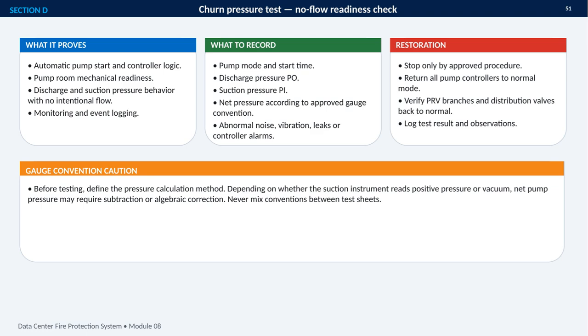During the test, I would record the pump mode and start time, discharge pressure, or P0, suction pressure, or P1, and the resulting net pressure using the approved gauge convention. I would also document any abnormal noise, vibration, leakage, or controller alarms. The gauge convention is especially important.